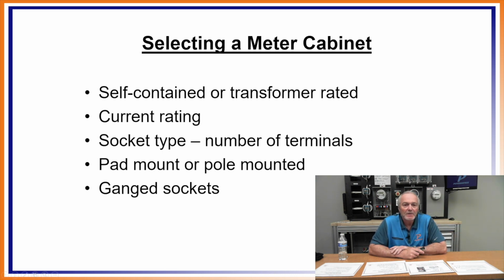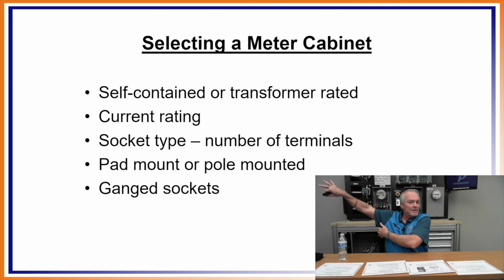Then the number of terminals that you need, the socket type, pad mount or pole mounted. That's also a key. They've got some pretty slick cabinets now that can be mounted both pad and pole mount. They've got these combo cabinets now. And then, of course, gang sockets. If you've got an apartment complex or something like that, I've got my main service disconnect, and I've got a whole bunch of sockets there. I've always got my main entrance point there, where I have my service entrance, but then I could have a whole gang of meters behind that, right?